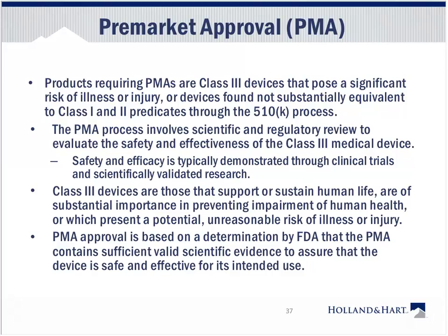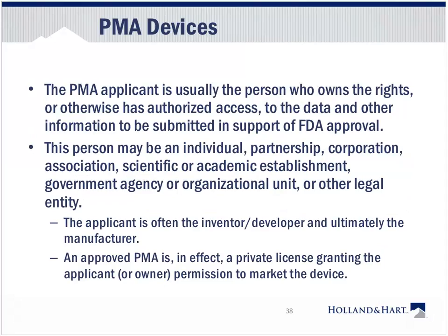Just try to remember that Class 3 devices are those that support or sustain human life, are of substantial importance in preventing impairment of human health, or which present a potential unreasonable risk of illness or injury. And the FDA will not approve such a device under the pre-market approval plan without sufficient valid scientific evidence to assure that the device is safe and effective for its intended use. Again, we're just not going to put a heart valve out there that hasn't been extensively studied through clinical trials. The same thing is true of any other device that has that kind of import on human life.